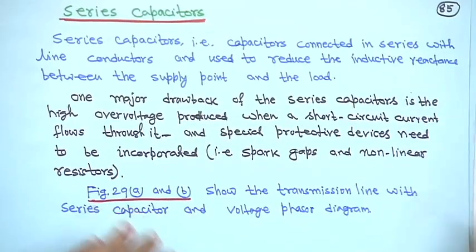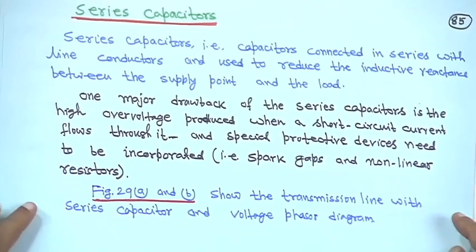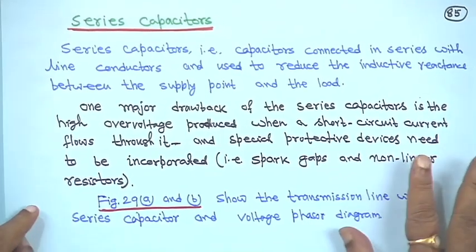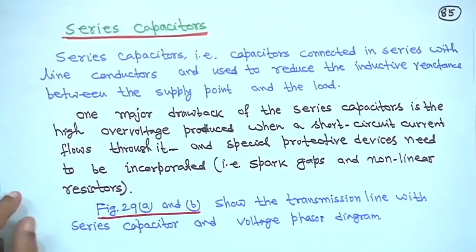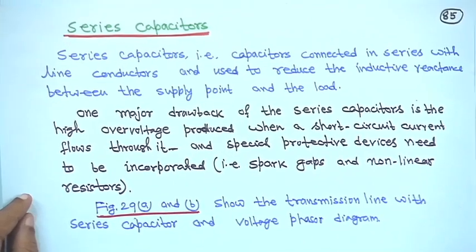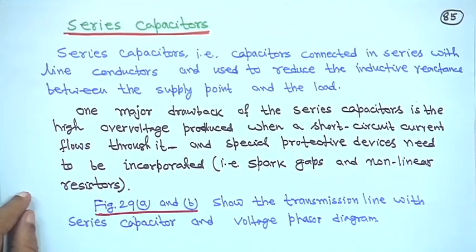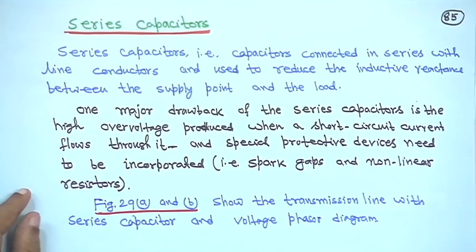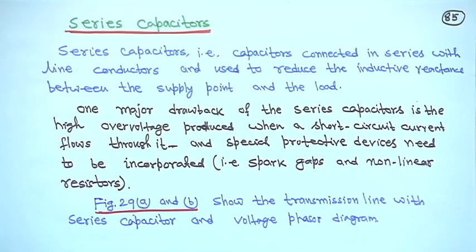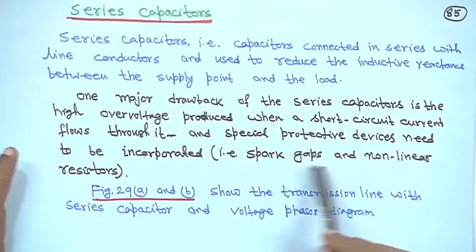Next is the series capacitor. A series capacitor is connected in series with the transmission line so that the inductive reactance is compensated by the capacitive reactance. Resonance is another problem for series capacitors. One major drawback of the series capacitor is the high overvoltage produced when a short-circuit current flows through it. Special protective devices such as spark gaps and non-linear resistors need to be incorporated.